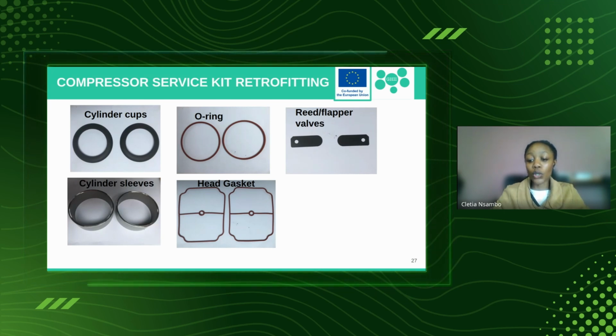For this, we had to collect data on the dimensions of the cylinder cups, sleeves, and reed valves. After collecting these dimensions, we noticed that for some compressors you can use cylinder sleeves from one compressor on another. That means you don't need the full compressor service kit for that particular model, because you can use parts from another compressor.